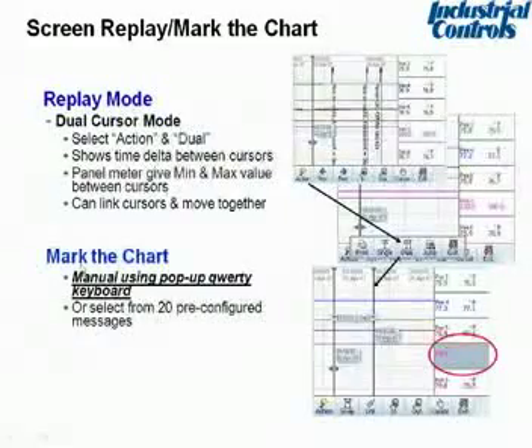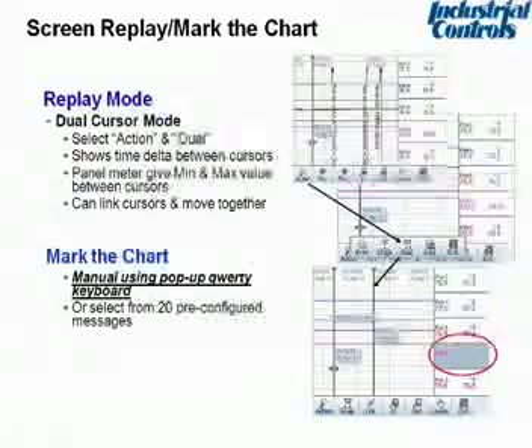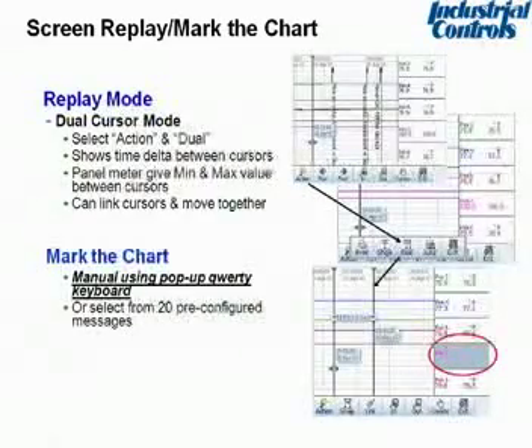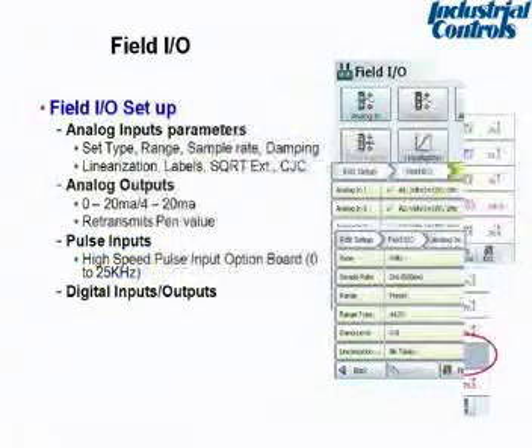You can also mark the chart, which is another neat feature. A lot of people ask me, Bill, I like the paperless, but how do I write on the paper chart? And the answer is, if you select that function on the front of the recorder, up will pop a QWERTY keyboard, and then you would go in and put that message, the operator's name, the fact that a thermocouple burned out, or whatever that might be. Here we see a power on, power off that's actually captured on the chart. And whenever you look at that chart on the recorder or at the archived data, you will now have captured those marks on the chart as part of the permanent history record.